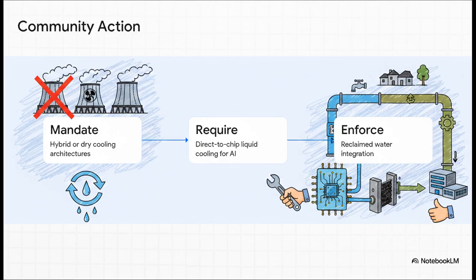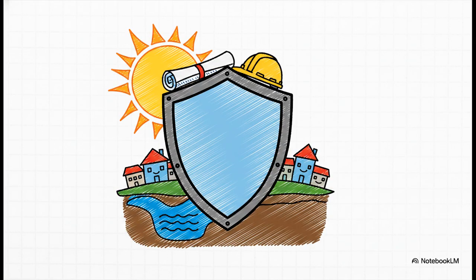Number 1, mandate hybrid or dry cooling architectures so they aren't constantly evaporating water. Number 2, require direct-to-chip liquid cooling for AI to capture heat efficiently. And number 3, strictly enforce the use of reclaimed or alternative water so they aren't drinking from the exact same tap as your community. You know, we really don't have to accept the old way of doing things anymore.